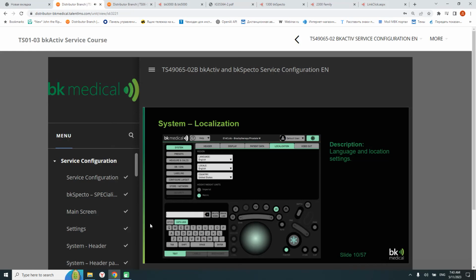The Localization tab is where language and local settings can be set. The Video Out tab is where the video out is set. Select the video out mode on the drop-down list and select Save. Video out can be off, cloned, or passive. Video out should only be enabled if it's being used. It is essential the external monitors support the resolution for the selected video out mode. The resolutions are defined in the service manual.